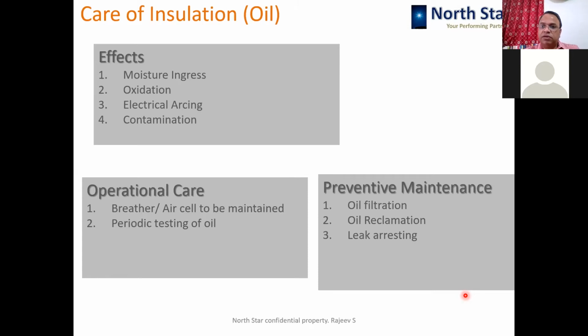Leakages are more serious. They are serious for the transformers, but they are more serious for your CTs, PTs, and EHV bushings. Those bushings and these components have very little volume of oil and they are very compact. So they also develop leaks, and when these things leak, because of the very little quantity of oil, even a smaller amount of moisture deteriorates the insulation considerably.